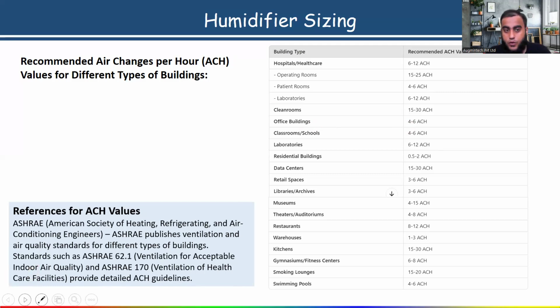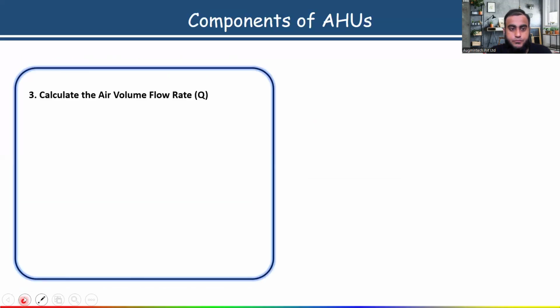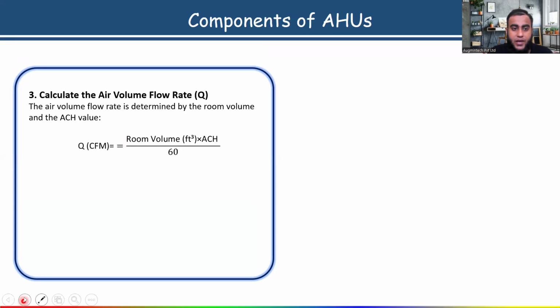Now come to the next step. We are talking about humidifier selection. Remember, okay? The first point I have discussed is to calculate the room volume in cubic feet. Once you get the room volume, now we need the ACH value. So from this table, you will get that value. Now the next step is what? Calculate the air volume flow rate. Okay. Now we have to calculate the air volume flow rate. So air volume flow rate is determined by the room volume and the ACH value. When you know the ACH, then only it is possible.